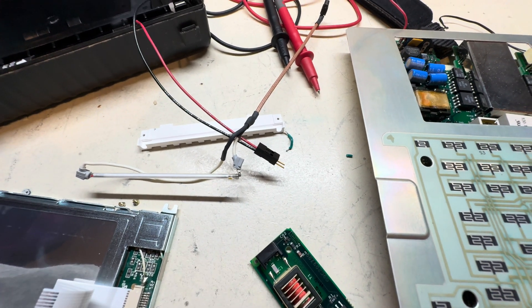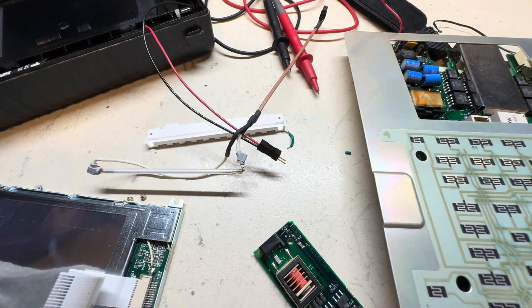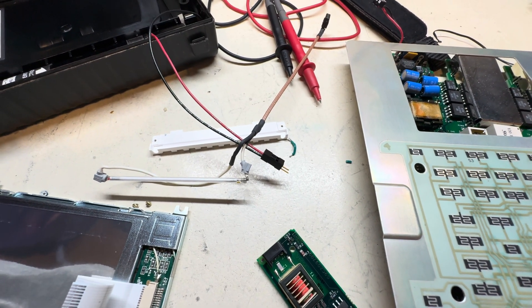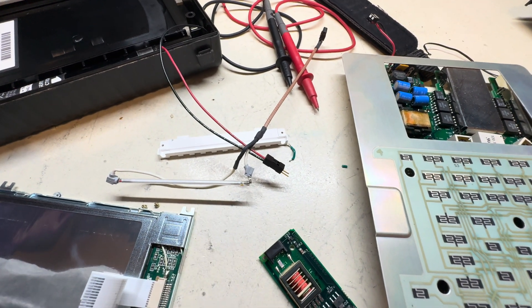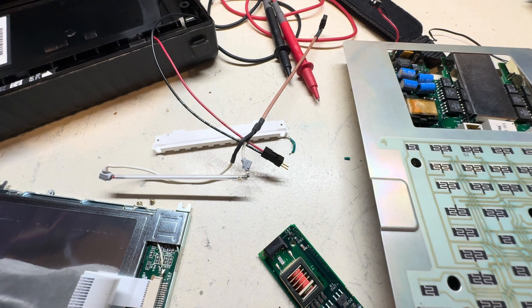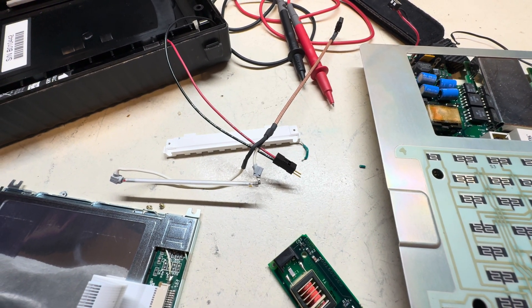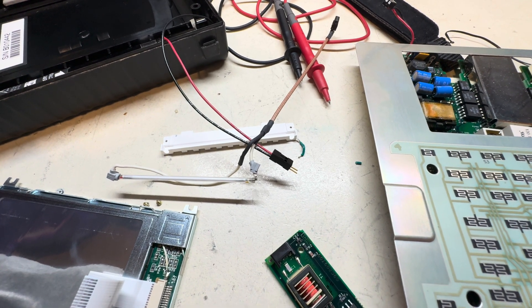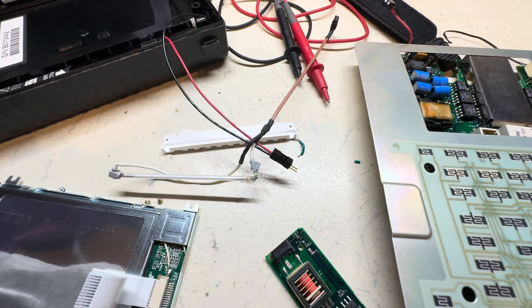The problem unfortunately is with the tube itself. I'm kind of surprised because I've seen much worse on other Tektronix equipment where the tube was completely black on both sides. This one failed, but the filament has likely opened up and the argon and mercury are not ionizing, so obviously you're not going to get any light. I do have to replace that tube to get this going.